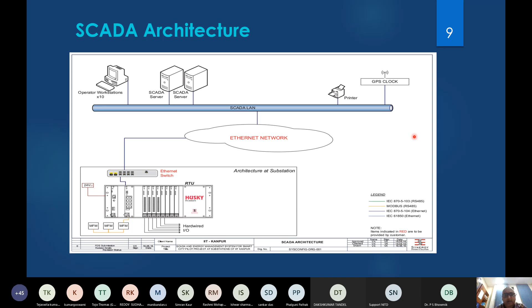By the way, you see this GPS clock here. All the RTUs - right now we have 12 RTUs - are GPS synchronized. The measurements that you have from the RTUs have a timestamp, and every few seconds or milliseconds, these RTUs are synchronized through the network time protocol.